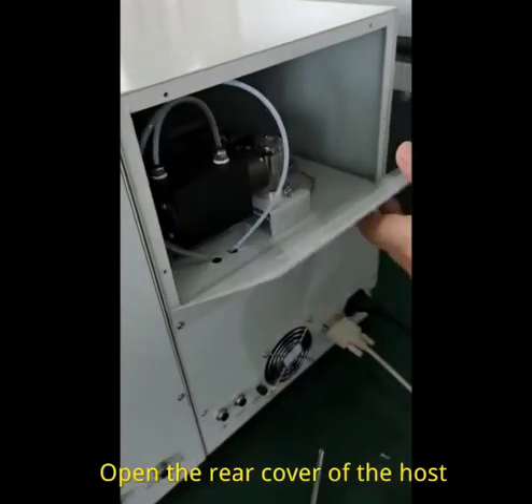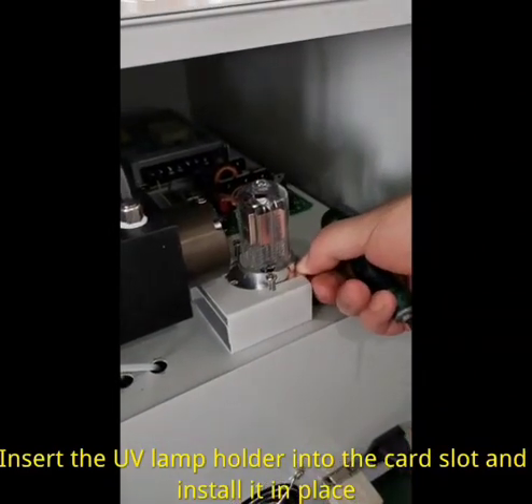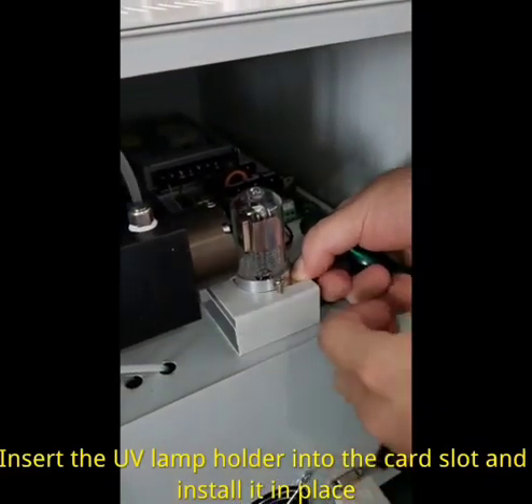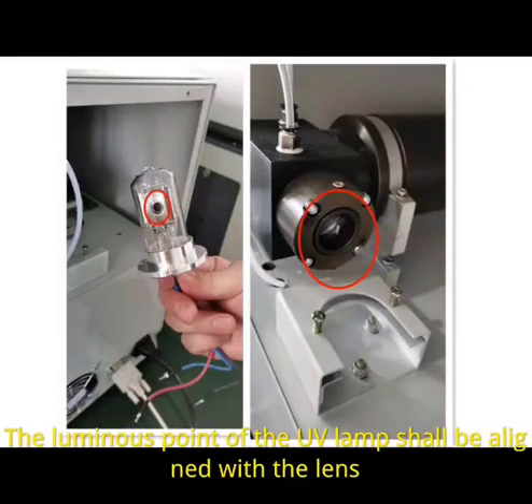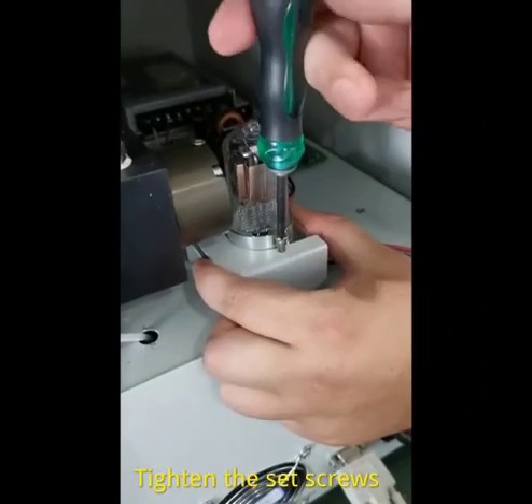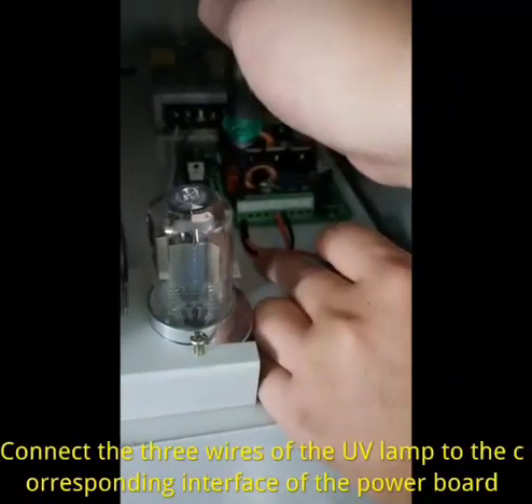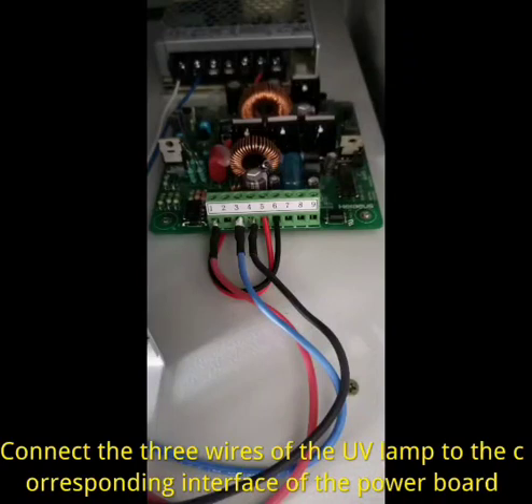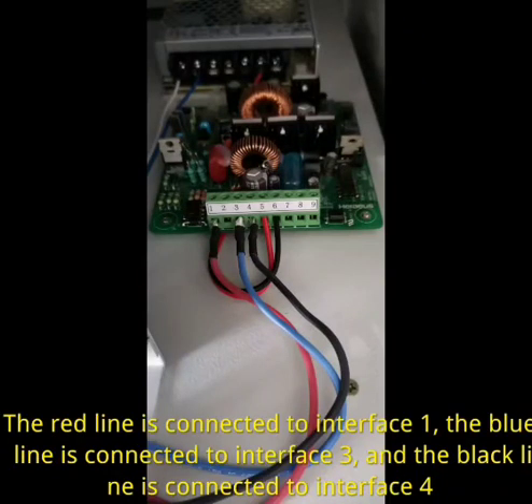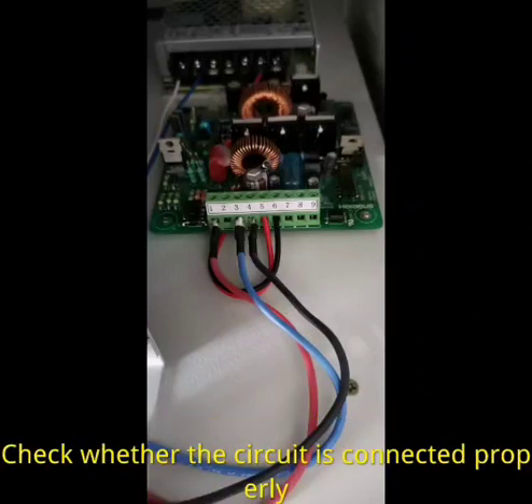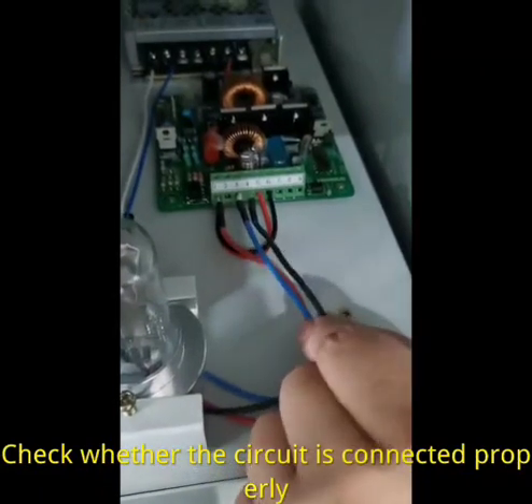Install the UV lamp. Open the rear cover of the host. Insert the UV lamp holder into the card slot and install it in place. The luminous point of the UV lamp shall be aligned with the lens. Tighten the set screws. Connect the 3 wires of the UV lamp to the corresponding interface of the power board. The red line is connected to interface 1, the blue line is connected to interface 3, and the black line is connected to interface 4. Check whether the circuit is connected properly.